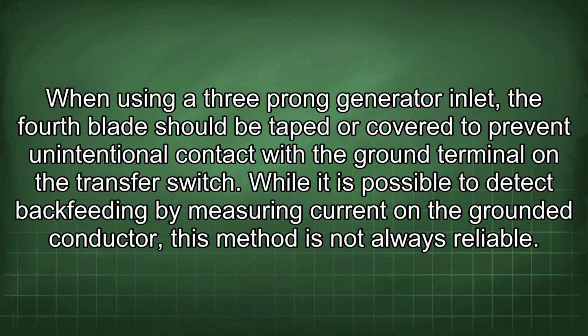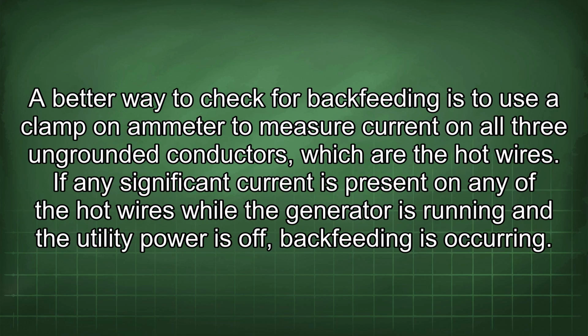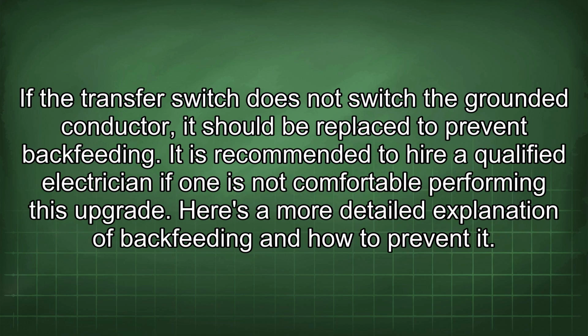While it is possible to detect backfeeding by measuring current on the grounded conductor, this method is not always reliable. A better way to check for backfeeding is to use a clamp-on ammeter to measure current on all 3 ungrounded conductors, which are the hot wires. If any significant current is present on any of the hot wires while the generator is running and the utility power is off, backfeeding is occurring. If the transfer switch does not switch the grounded conductor, it should be replaced to prevent backfeeding. It is recommended to hire a qualified electrician if one is not comfortable performing this upgrade.